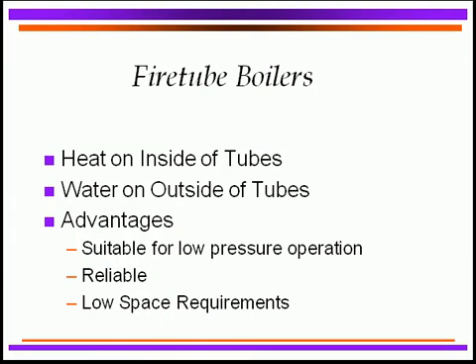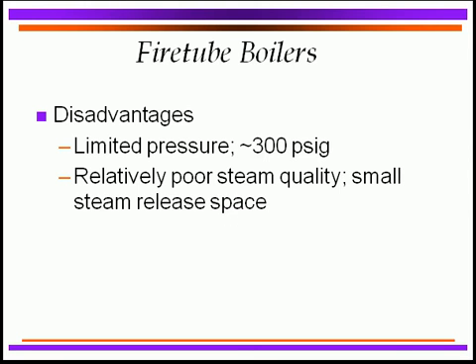The advantages of these fire tube boilers are that they are good for low pressure operation. They're very, very reliable and have been used for years. They do require only a small space for operation, so consequently that is a major advantage. There are some disadvantages of the fire tube boilers. The major ones are they're limited on pressure — we seldom get over 300 PSI, maybe just a little bit over, but generally speaking, we hold it to a maximum of 300 PSI.